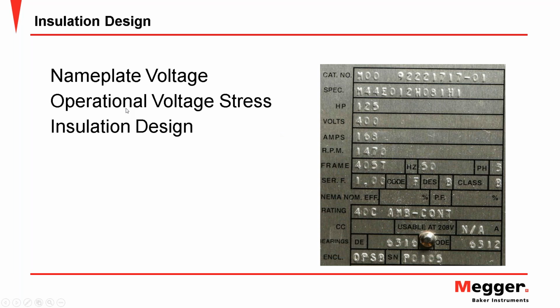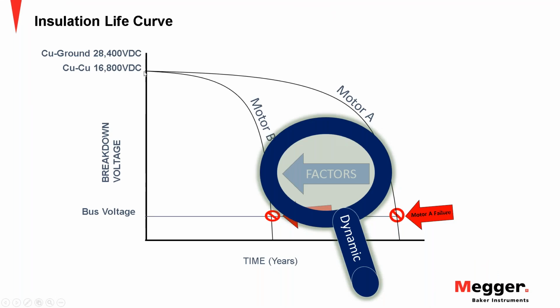And then we also have to consider the actual stress that the motor has to endure. While we're applying 400 volts, during the make and break of the contactor we have voltage spikes or operational voltage stresses that far exceed that nameplate voltage. There's documented evidence, empirical data collected in the field by engineers, that shows that value can be as high as 4 times the nameplate voltage. So there's a significant potential stress there that goes well beyond that of the nameplate. And then of course we have the voltage associated with insulation design, and that was the graph I just showed you prior. At the beginning of life we want a very high insulation integrity, breakdown voltage, if you will.